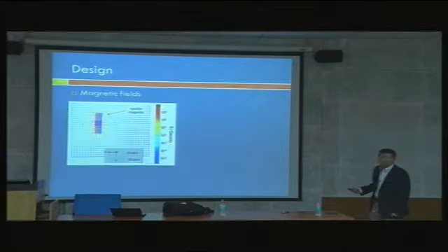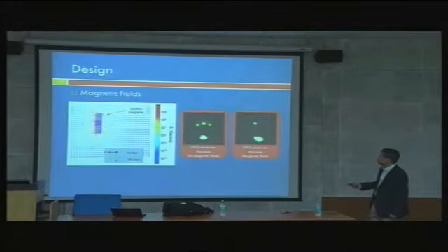This is a COMSOL simulation, and you can do a lot of electromagnetic simulation of the sputter magnet, which creates a lot of magnetic field. Without the magnetic field, your spot is very symmetric here. But when you bring in the magnetic field, the beam is bent like this, so it's not very symmetric.